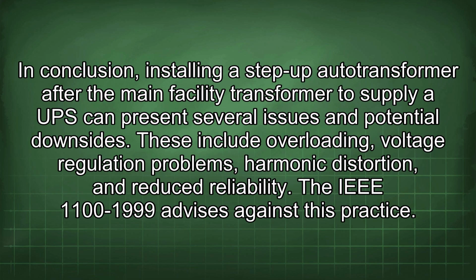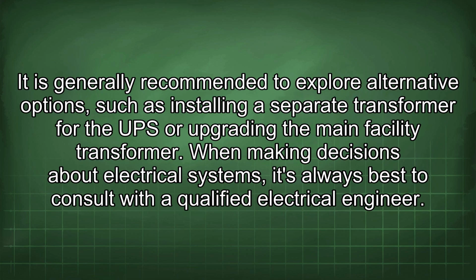In conclusion, installing a step-up autotransformer after the main facility transformer to supply a UPS can present several issues and potential downsides. These include overloading, voltage regulation problems, harmonic distortion, and reduced reliability. The IEEE 1100-1999 advises against this practice. It is generally recommended to explore alternative options, such as installing a separate transformer for the UPS or upgrading the main facility transformer. When making decisions about electrical systems, it's always best to consult with a qualified electrical engineer.